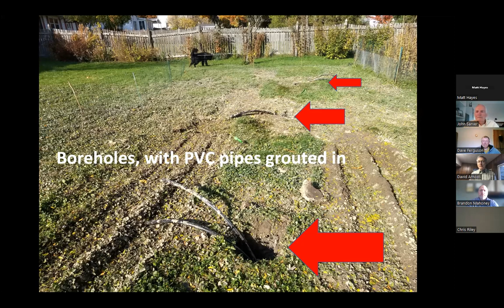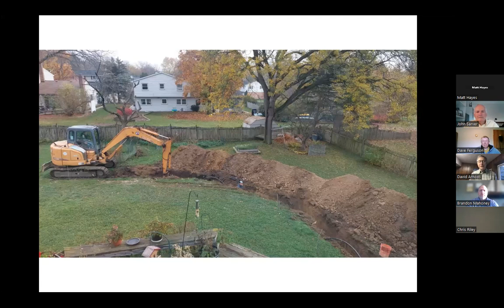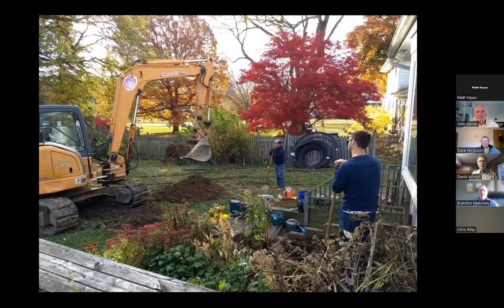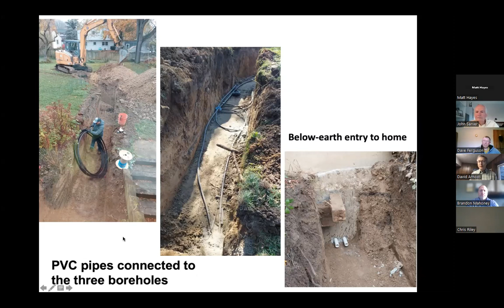So the driller left the backyard with some tire tracks and these 3 boreholes. Then Michigan Energy Services team came out and finished the job using an excavator. They trenched down to, I think, 5 feet, tied all the plastic tubing together, and brought it right up to our house. You can see them connecting this plastic tubing, and then it goes to these 2 white tubes into our basement. That allows the liquid to circulate back and forth underground, during the winter well below the frost line.